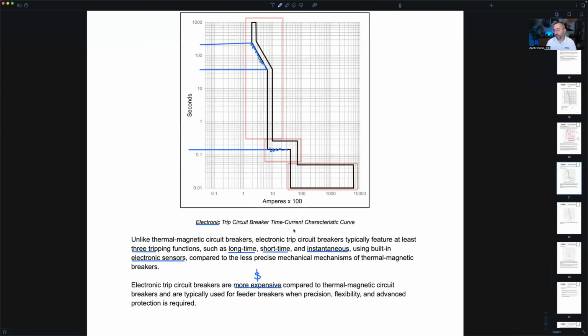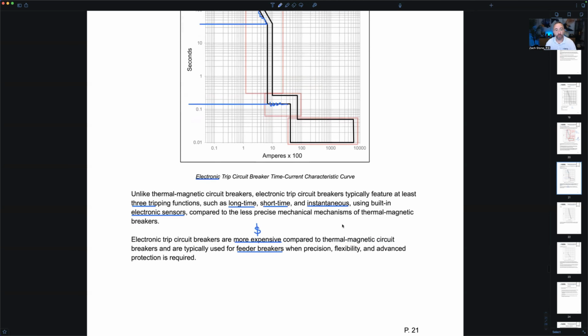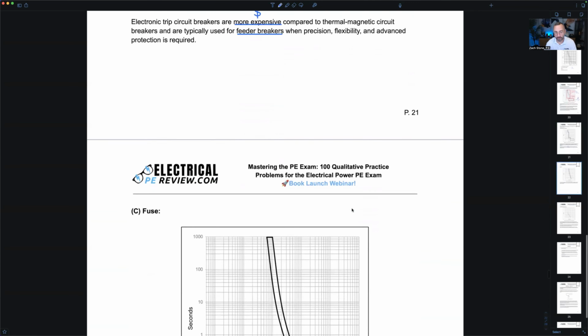Let's see. Brooklyn said, yeah, usually the thermal mag just needs to protect small motors or small loads. Don't need complex protection. Exactly. What are these typically used for? When do I want more flexibility? A lot of times you got big feeder breakers, right? So thermal mags, a lot of times we use them for branch circuit protection, the last overcurrent device in that circuit. What about if I've got a big feeder breaker that feeds a panel and that panel feeds 40 some loads? Well, maybe that one feeder breaker is protecting all of those loads connected to the panel. So I want to be able to have more customization. I want to be able to really fine tune the protection of that entire panel fed from the feeder breaker. So feeder breakers a lot, you're going to have more sensitive, more complicated, more sophisticated protection.